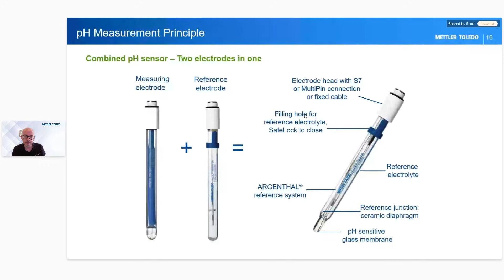In this diagram, you can see the outer glass bit. This outer glass is the reference part, and it's full of electrolyte inside. It has a little junction here that you might be able to see in the picture. Then in the center, you can see this second piece, which pops out at the end, and this is the measuring part. This glass is ever so slightly tinged yellow, whereas the outer is clear glass. This is the pH-sensitive glass membrane, covered in a gel, and it shoots up in the middle of the electrode. When we see combination electrodes, that's what we mean: we've just put them both together. Nowadays, for 90 to 95% of measurements, most electrodes used are combination electrodes.